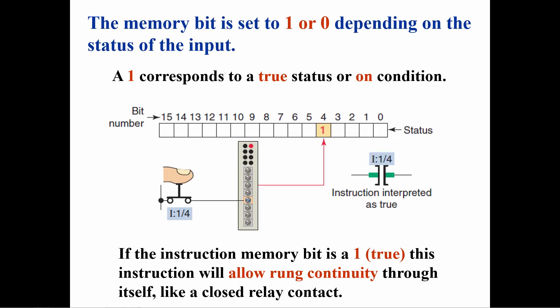The examine if closed instruction behaves very much like a normally open relay contact. When an external switch is closed, a 1 is placed at the address of the switch in the input table, and the examine if closed instruction becomes true and allows rung continuity, much like a normally open relay contact will allow current to flow when its coil is energized.